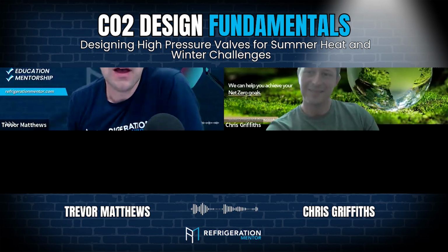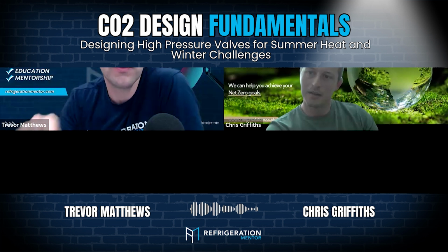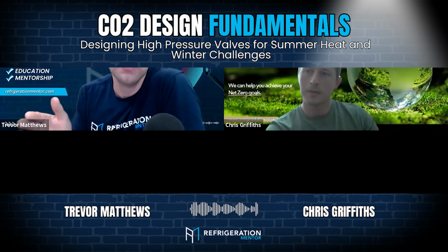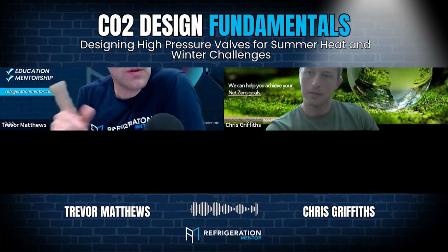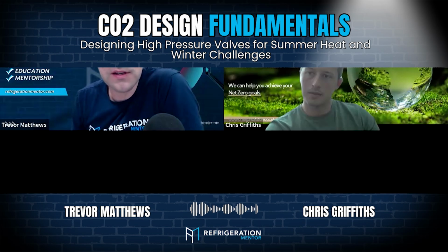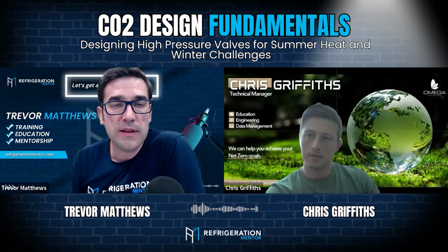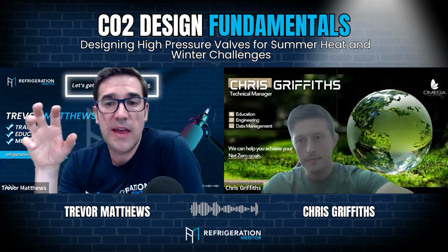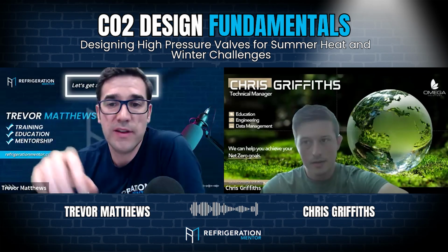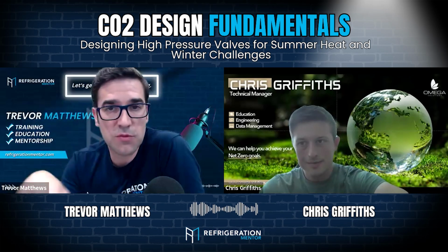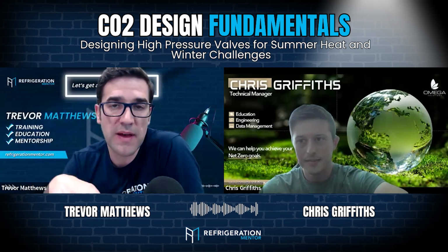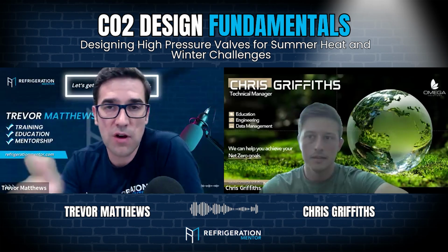Yeah. I think I did a podcast with my good friend Timo Kofo, when he used to work for Carel. So go check it out on the YouTube channel. That's not more on the design side. Well, it kind of is. It's on how to use it, where the contractor pulled off the head of the Carel valve and it's still adjusting and you still think it's moving, but it's actually not moving.